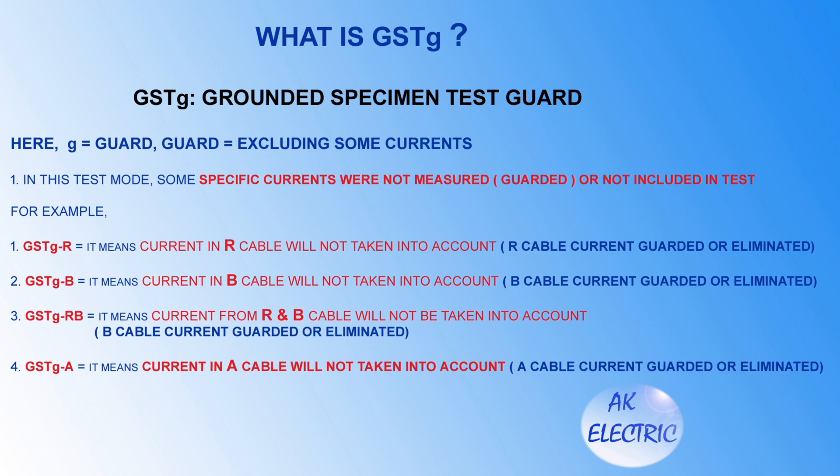GSDGB means the current in the blue cable will not be taken into account — blue cable current is guarded or eliminated. GSDGRB means current from both red and blue cables will not be taken into account — both are guarded or eliminated. GSTg-A means the current in the A cable will not be taken into account — A cable current is guarded or eliminated.